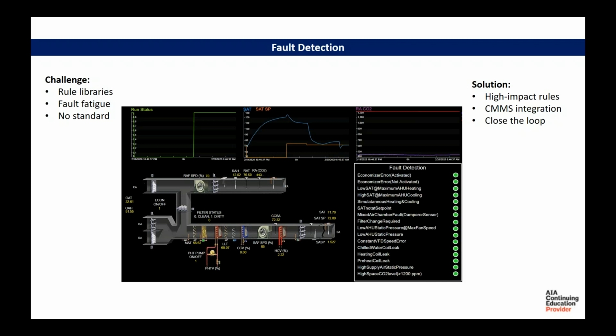So how do you integrate FDD into your existing workflows? The most effective approach is a phased deployment, where you focus on high impact, high probability faults and deploy them campus wide. That's based on industry guidance and also my personal experience. There's a small subset of fault detection rules, and this is true for air handlers, chillers, and boilers, that deliver 80% or more of the value.